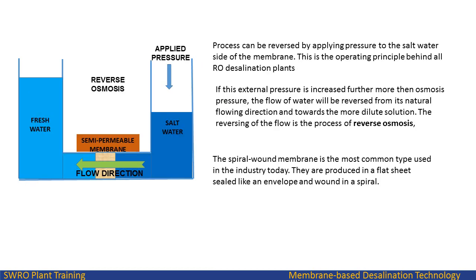The process can be reversed by applying pressure to the salt water side of the membrane. This is the operating principle behind all RO desalination plants. If this external pressure is increased further beyond the osmotic pressure, the flow of water will be reversed from its natural flowing direction and towards the more dilute solution.